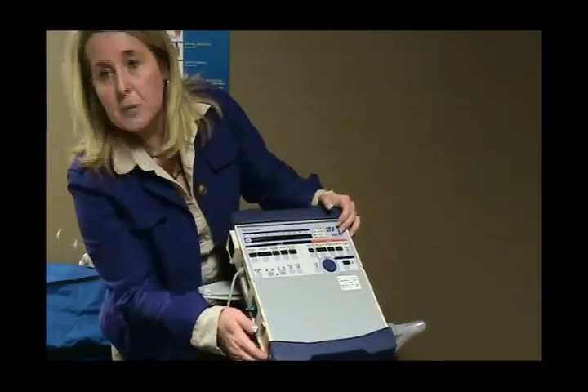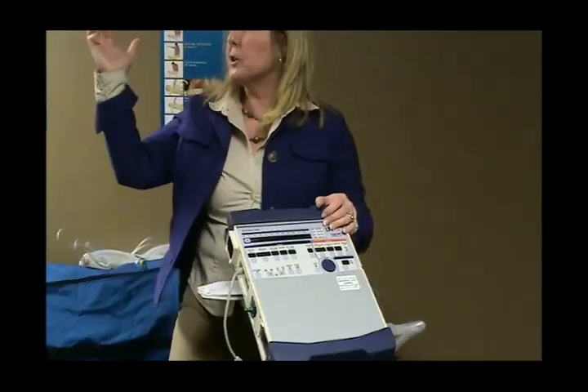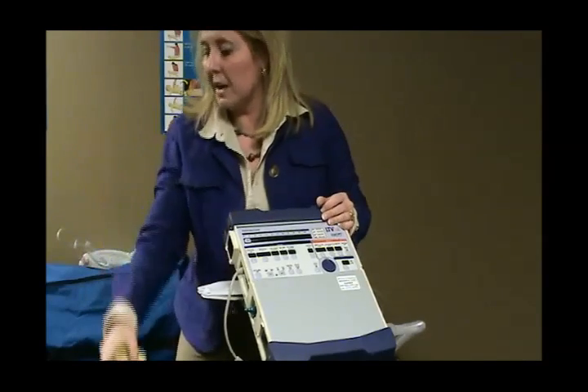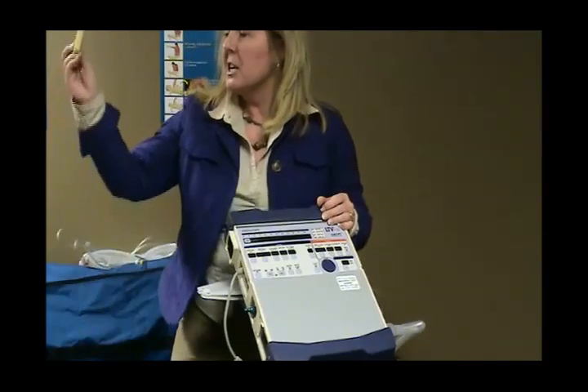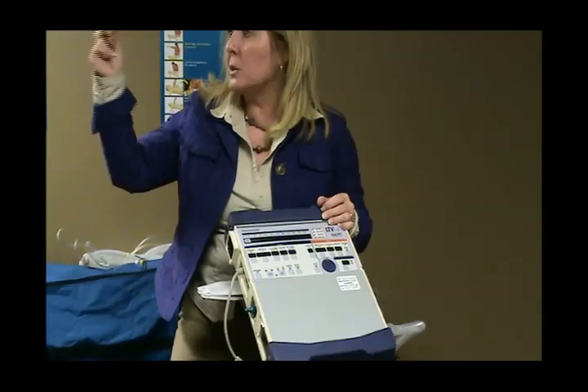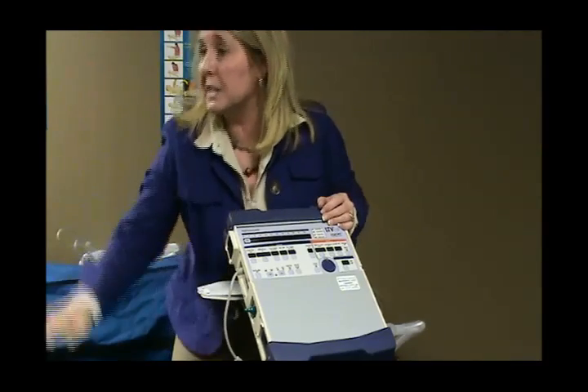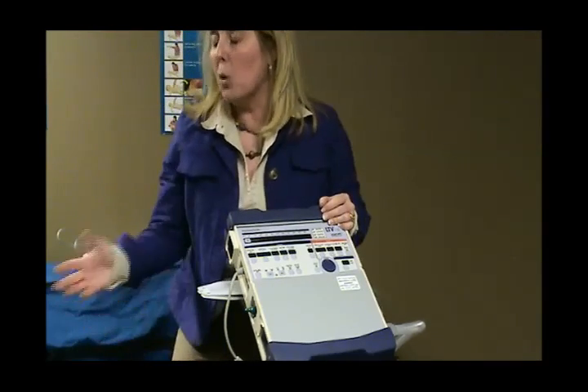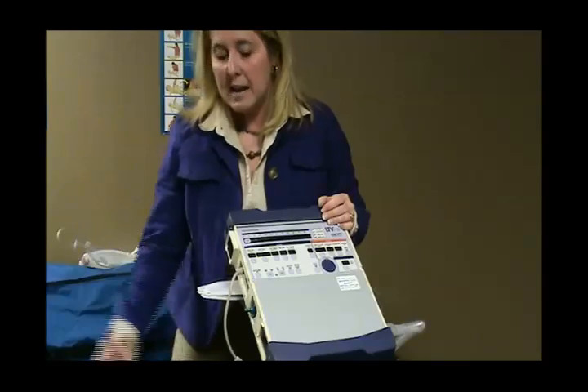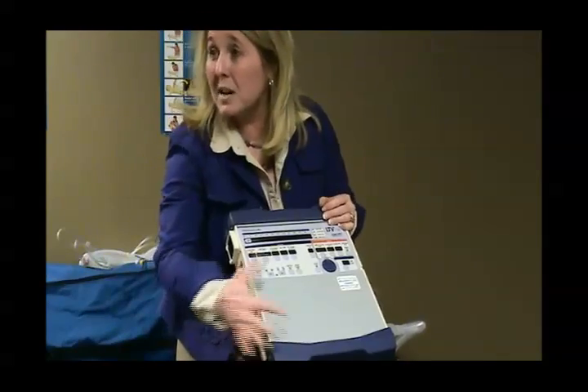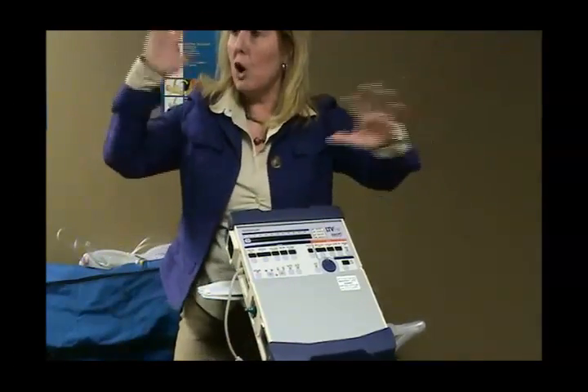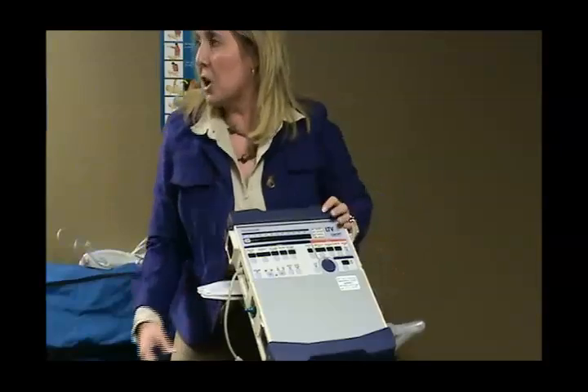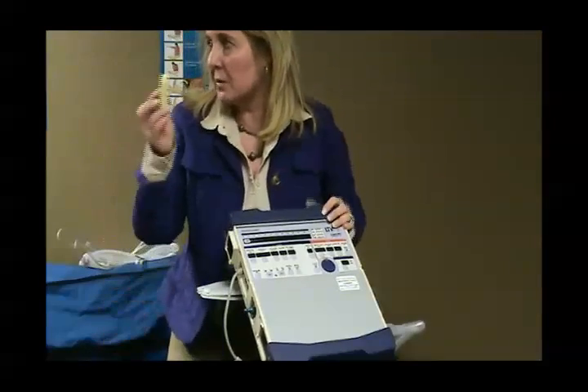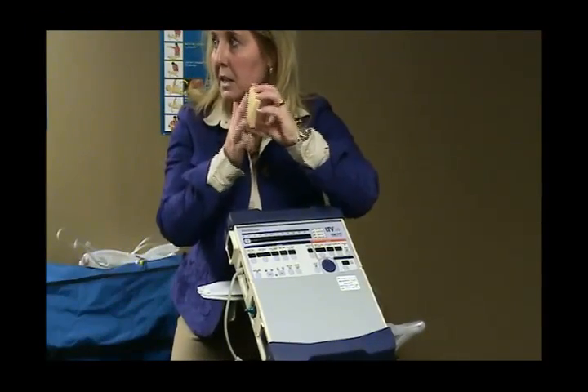Yep. Second filter, the foam filter. This is the color it's supposed to be, not this color. Okay? So it needs to be washed out once a week with warm soap and water. You squeeze it out, you let it air dry. You don't put it back in there until it's dry. That is the filter that protects the ventilator from large particles flying around in the room, like dog hair and cat hair and that kind of stuff. It's the stuff you'll see deposited on the outside of this.